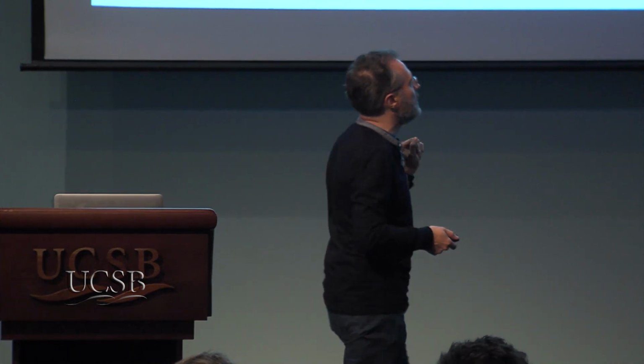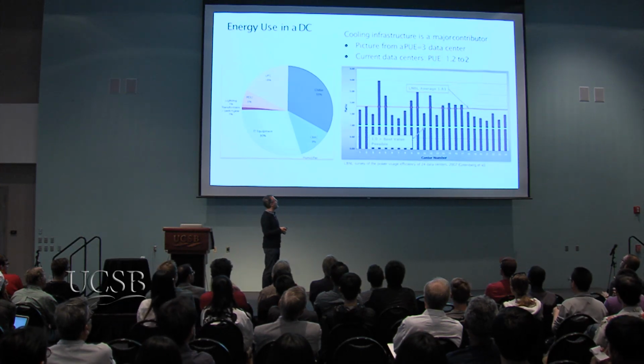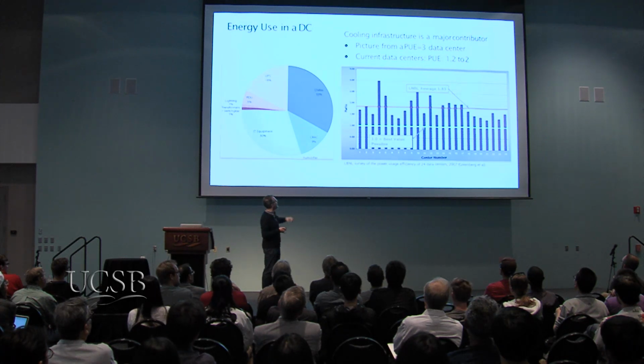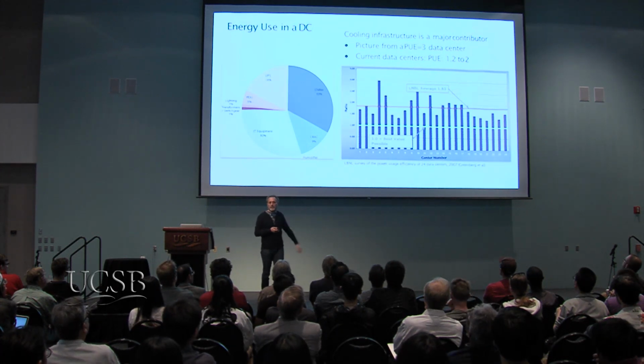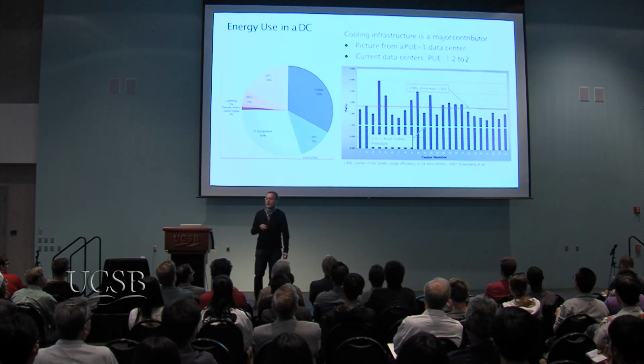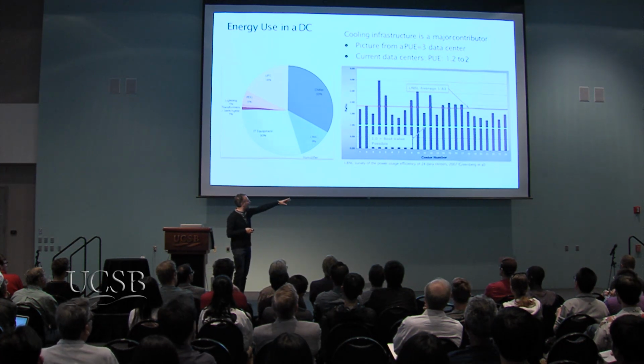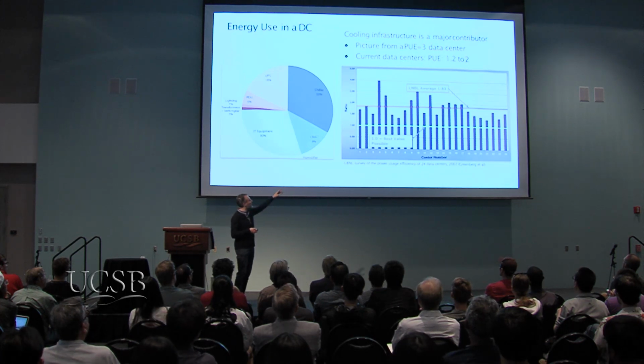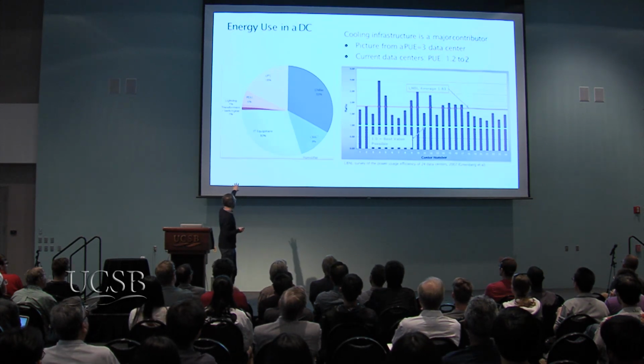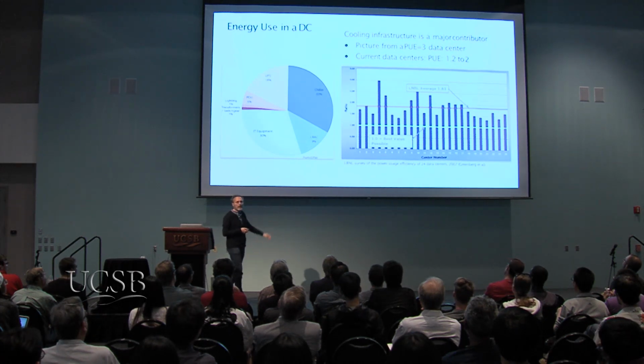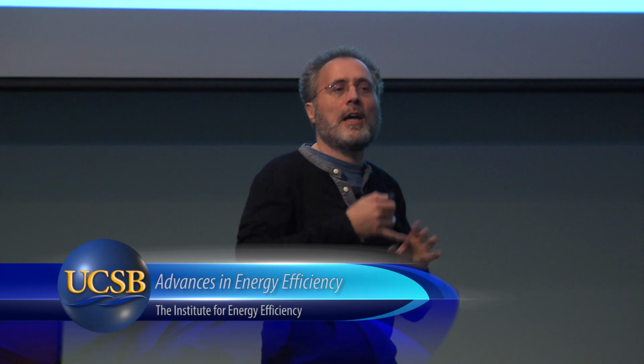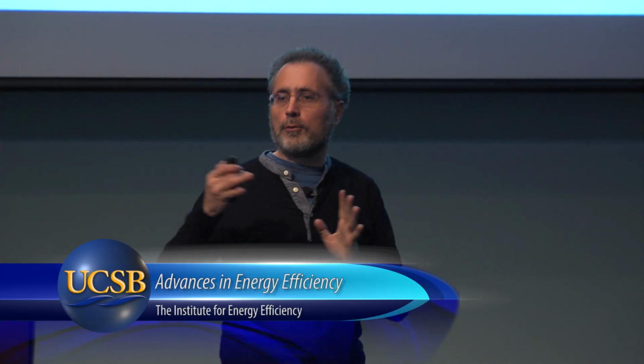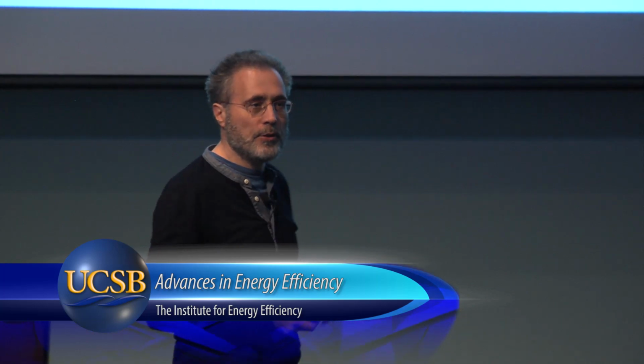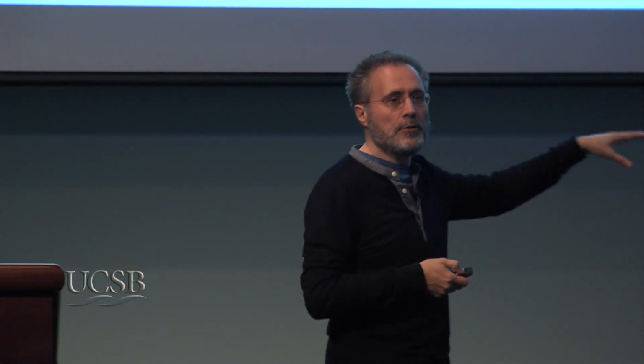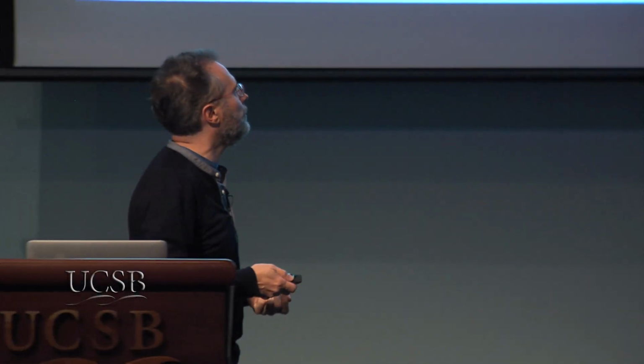Here's a study of larger data centers that Lawrence Berkeley Labs did. The theory was that larger data centers run more efficiently. They looked at 24 different data centers and saw an average overhead factor of 1.8, a bit better than the factor of 3 we saw before. A factor of 1.8 means 55% of energy goes to the actual IT load and 45% to other stuff. So every server you introduce still gets multiplied by 1.8 in energy consumption just because it's in a data center.